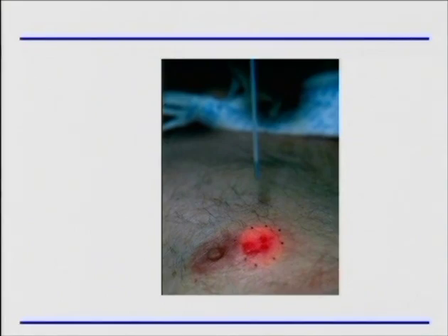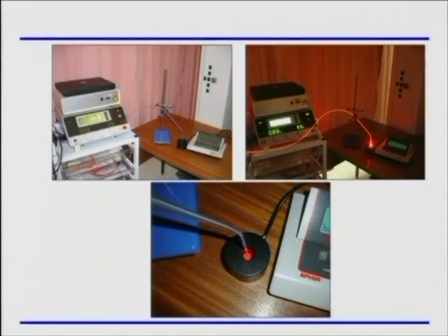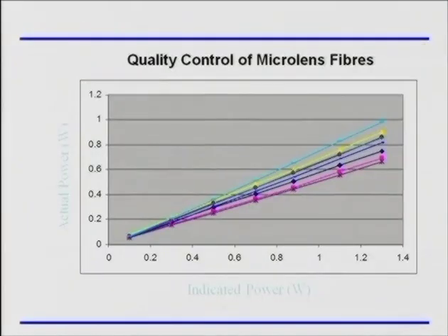In actual fact, it's much simpler in this case to measure what's coming out of the fiber. All you need to do is use a simple laser power meter, and provided you only fill about half to 2/3 of the surface of your thermopile, then you can easily collect all of the power coming out of the fiber, and you can make corrections for the amount that is reflected. So again, with some very simple equipment, you can now say, yep, I can measure how much power is coming out the end of this fiber. So use an integrating sphere if you're using a diffuser, or a simple power meter if you've got end of fiber delivery, and you can now begin to say with confidence how much power is coming out.